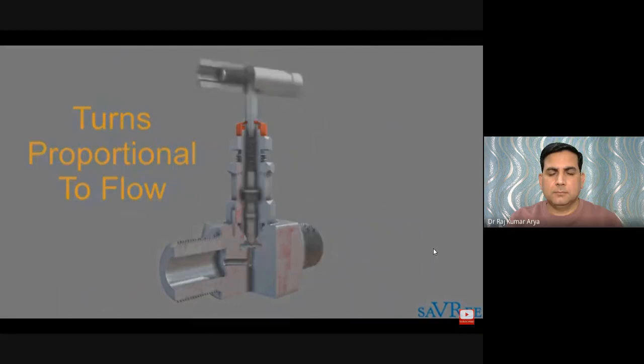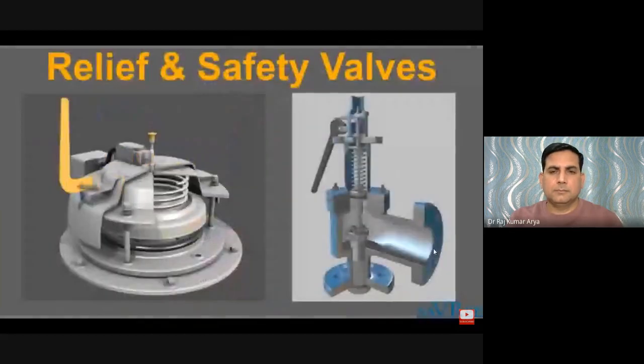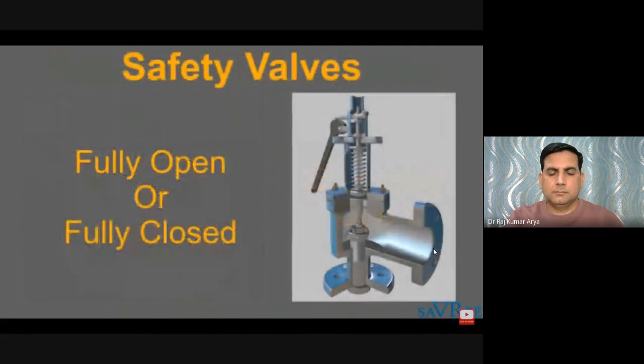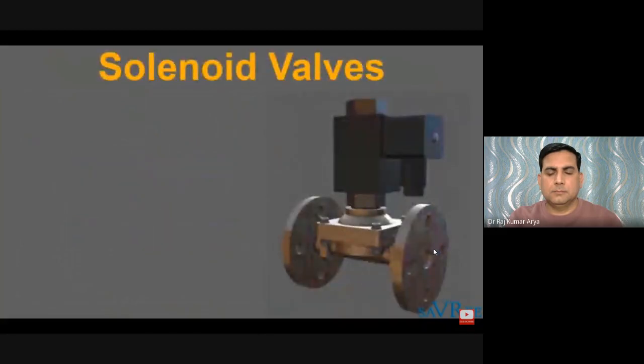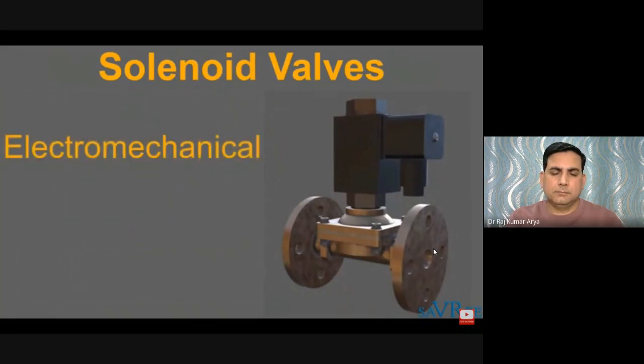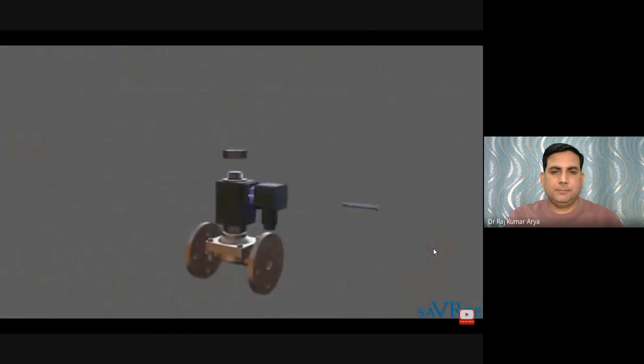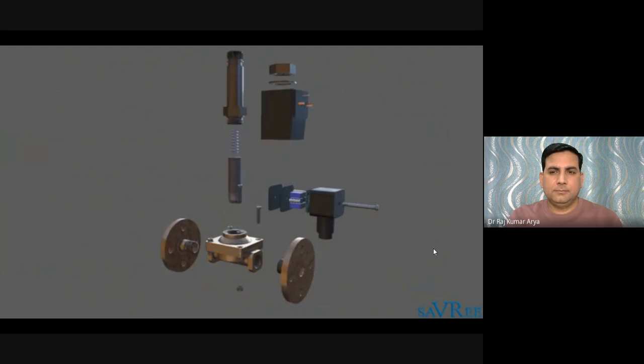Relief and safety valves prevent equipment damage by relieving accidental system overpressurization. A relief valve gradually opens as inlet pressure increases above the set point, opening only enough to relieve the overpressure condition. A safety valve rapidly pops fully open as soon as the pressure setting is reached and stays fully open until pressure drops below a reset pressure. Solenoid valves are electromechanically operated valves well suited to opening and closing operations. They can start or stop flow but are not well suited for regulating flow. An electromagnet operates the valve when current is supplied, and a spring returns the valve to its fail-safe position when current is no longer present.